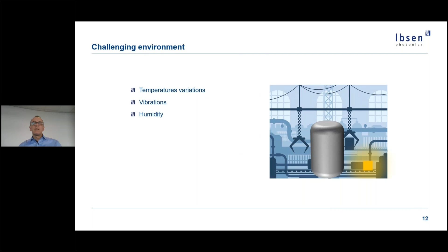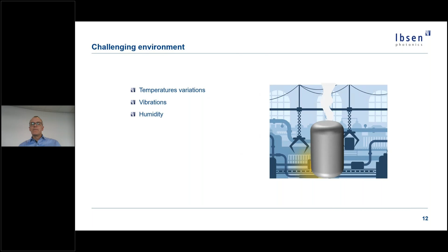To summarize, industrial spectrometers should ideally be easy to operate, not need calibration, and operate with zero downtime. An extra challenge for the spectrometers used in industry is the environment. In contrast to the lab, the temperature in a factory can vary a lot due to seasonal variations or neighboring machinery heating or cooling. Also, a spectrometer might be mounted at or near a vibrating machine like a pump, or it could be handheld. And finally, the humidity can, just like the temperature, vary quite a lot in a factory. So how do we address all these challenges? In the next part, I'll discuss how the spectrometer can be designed for industrial use cases.